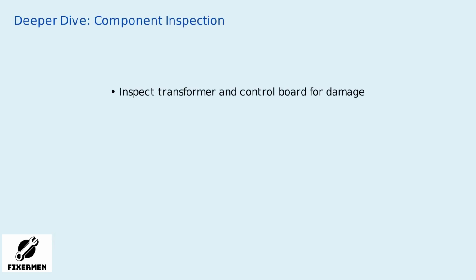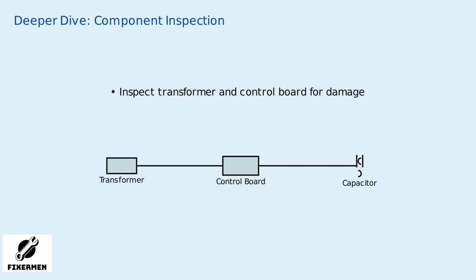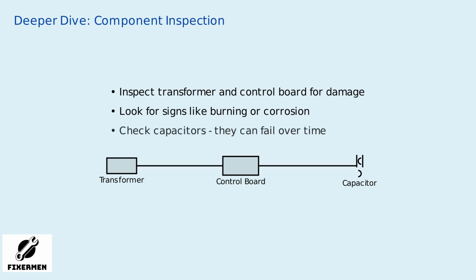If the reset doesn't resolve the P1 error, it's time for a deeper inspection of key components. Start by carefully examining the transformer and control board. Look closely for visible signs of damage, such as burning marks or corrosion, that could indicate electrical issues. Capacitors are particularly prone to failure over time, which can cause voltage irregularities leading to the P1 error. Test capacitors using a multimeter or dedicated capacitor tester to check for proper function.